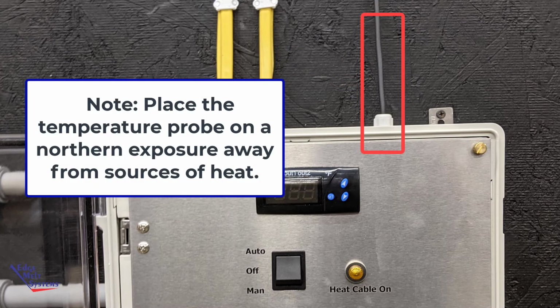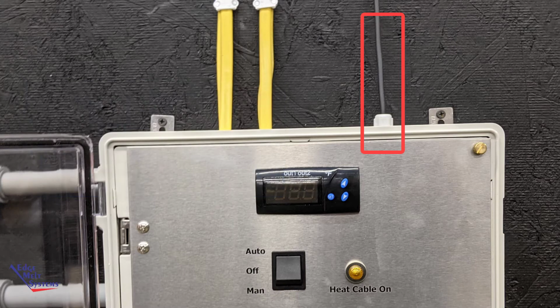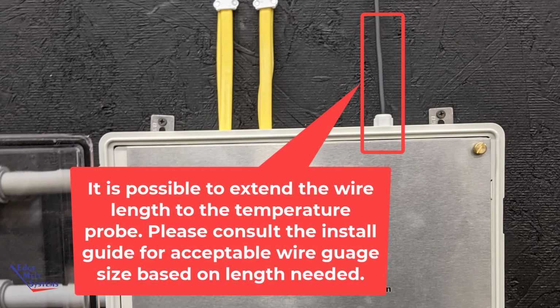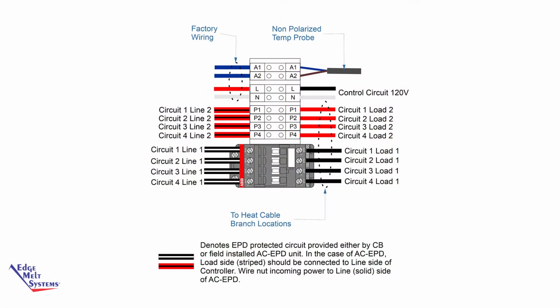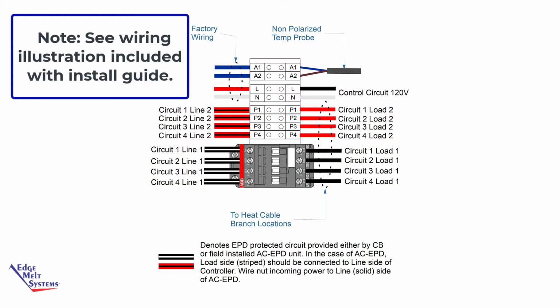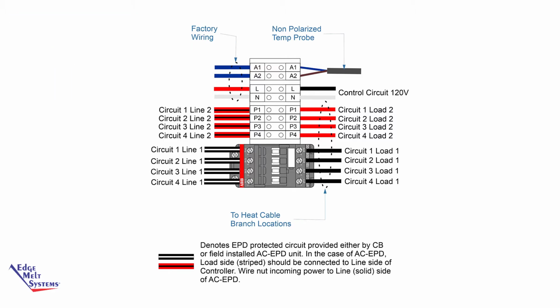It should be placed on a northern exposure away from any heat sources so that it can truly read outdoor ambient temperature. If you do need to extend the temp probe, you can do that using standard wiring. There are indications as far as gauge size depending on how far you will be extending the temp probe. There is a wiring illustration provided in the install guide included with each control panel.